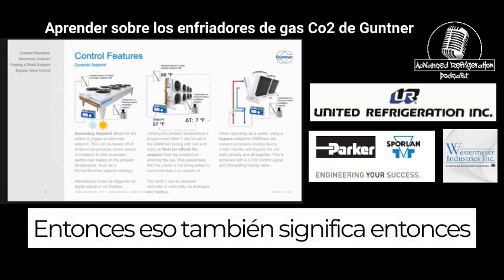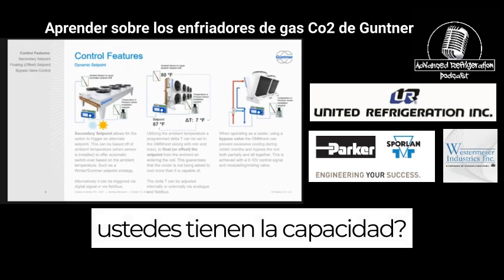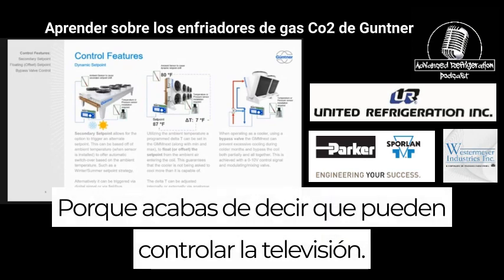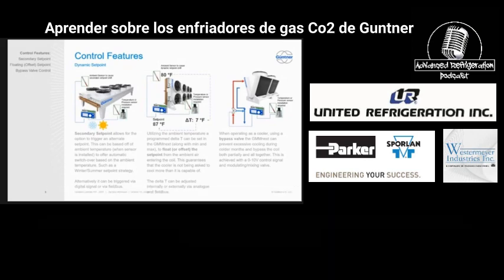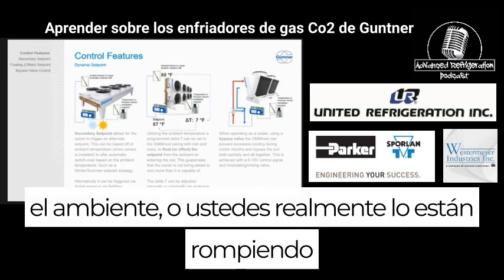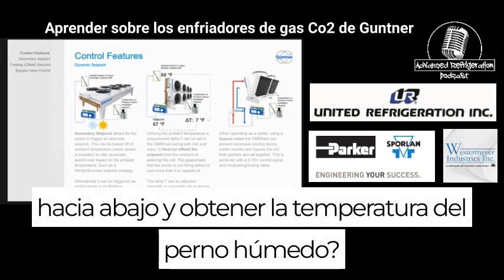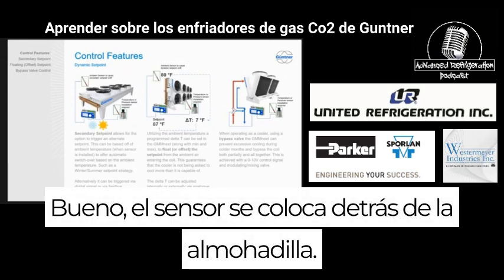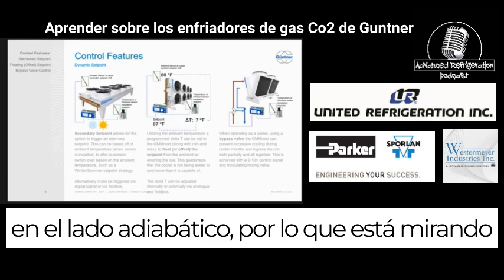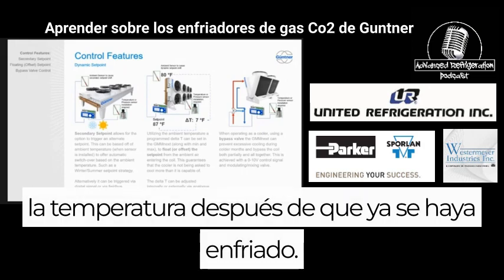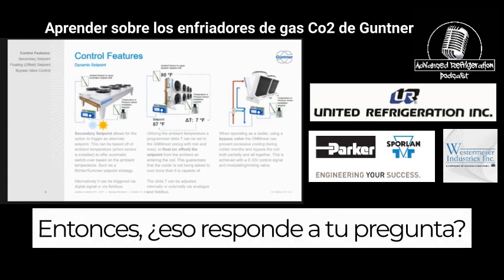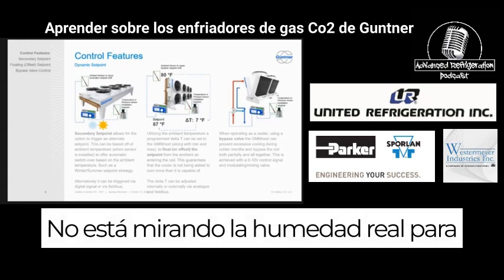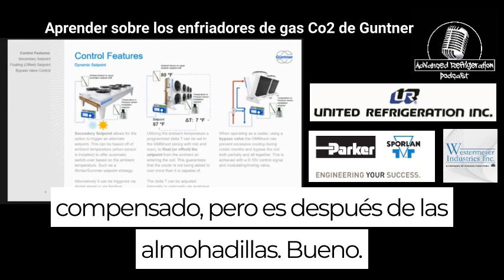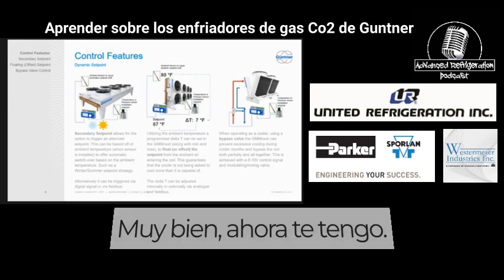So does that also mean then you guys have the capability, because you just said it can do TD control. Are you doing TD control just based off the ambient, or are you guys actually breaking it down and getting the wet bulb temperature? Well, the sensor is placed behind the pad on the adiabatic side. So it's looking at the temperature after it's already been cooled. So does that answer your question? It's not looking at the actual humidity to offset, but it is placed after the pads. Oh, okay. All right. No, I got you.